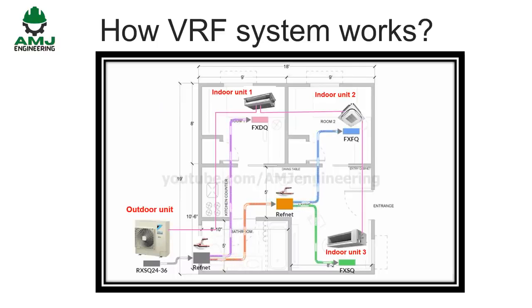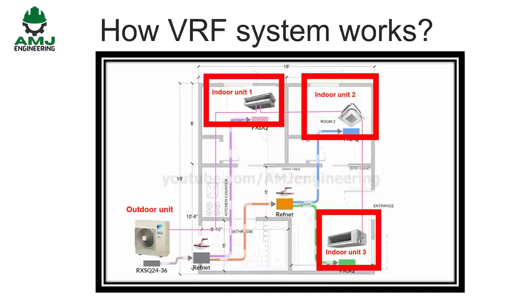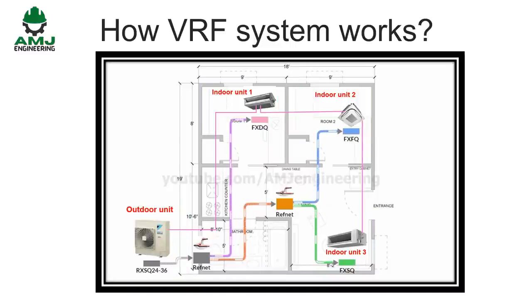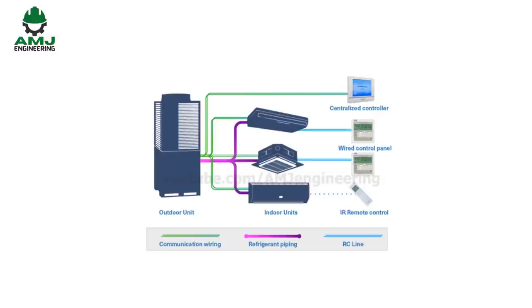A typical VRF system consists of an outdoor unit, several indoor units, refrigerant piping running from the outdoor to the indoors, using ref net joints, which are copper distributors and pipes, and communication wiring. Communication wiring comprises a two-wire cable chain from the outdoor to all indoors, creating an internal closed-loop network. This is an essential part of any VRF installation. As for the control, each indoor is controlled by its own wired control panel, while there are some possibilities for wireless remotes and centralized controllers, enabling control of all indoors from one location.